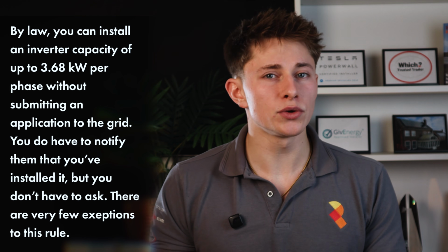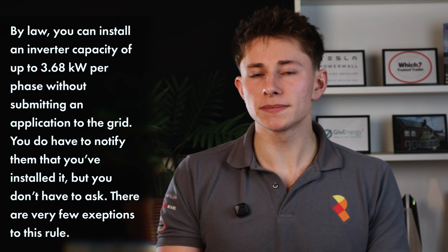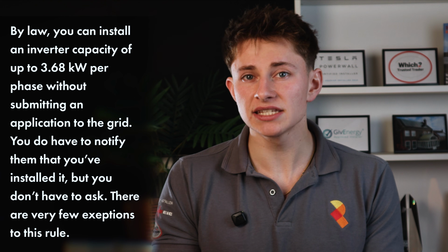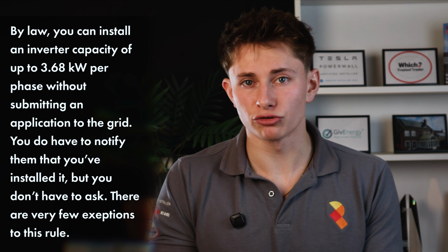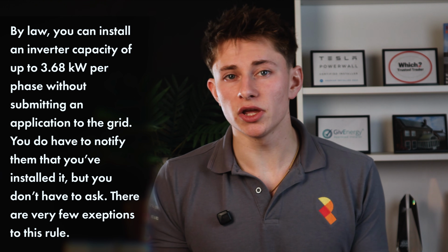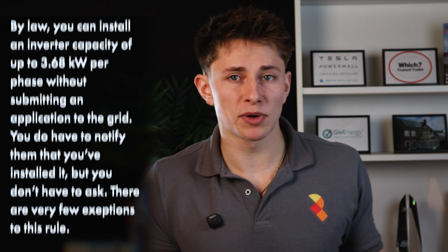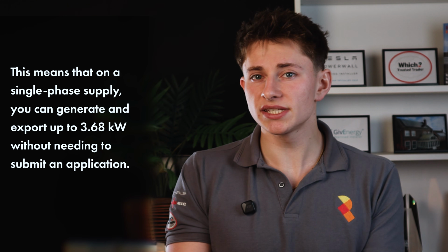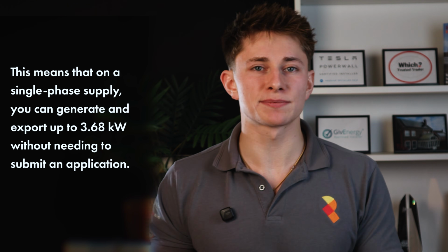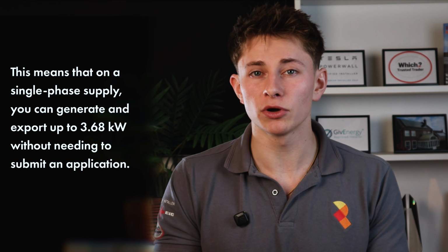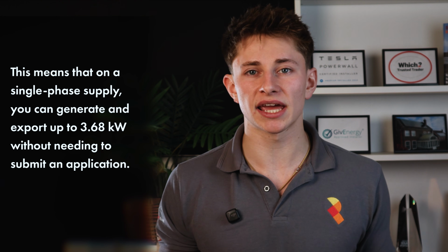Now, by law, you can install an inverter capacity of up to 3.68 kilowatts per phase without submitting an application to the grid. You do have to notify them that you've installed it, but you don't have to ask permission. This means that on a single phase supply, you can generate and export up to 3.68 kilowatts without needing to submit an application.